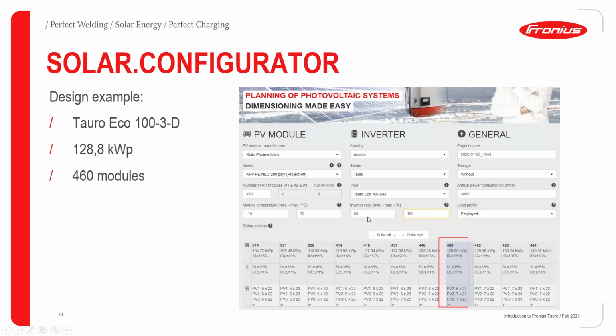Normally in this solar configurator, the inverter ratio is minimum chosen as 80 and maximum as 120. Of course, you can change this yourself, up to 150. The maximum DC possibility with the 100 kilowatt unit is 150 kilowatt DC.